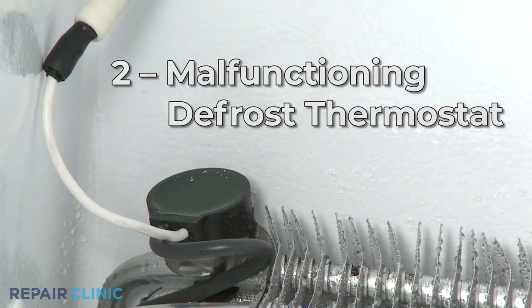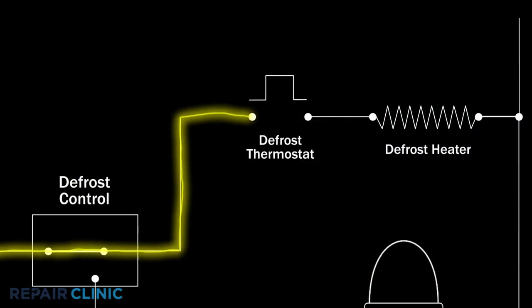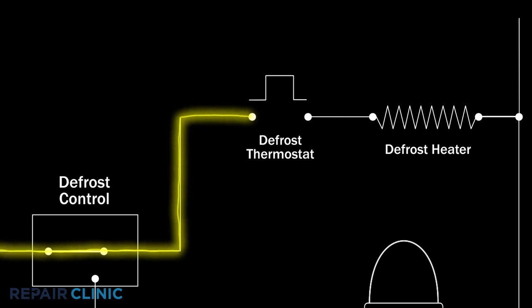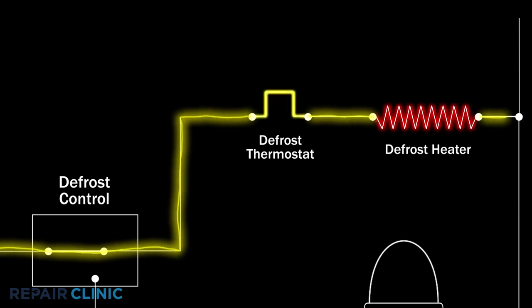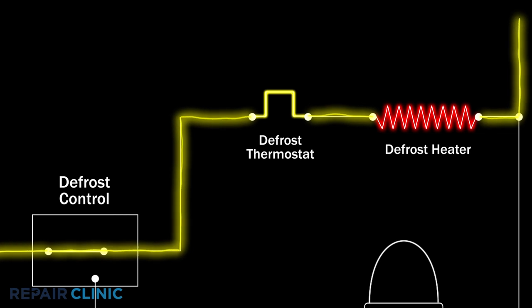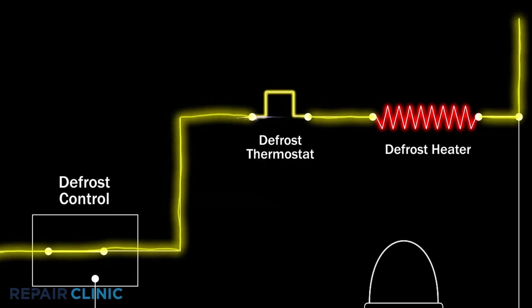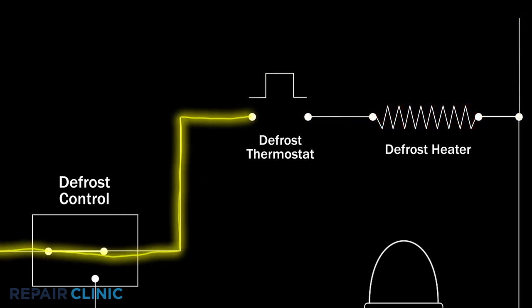The defrost thermostat monitors the temperature of the evaporator coils. When the temperature drops to a set level, the contacts in the thermostat close and allow voltage to power the defrost heater. A malfunctioning thermostat may prevent the heater from working.